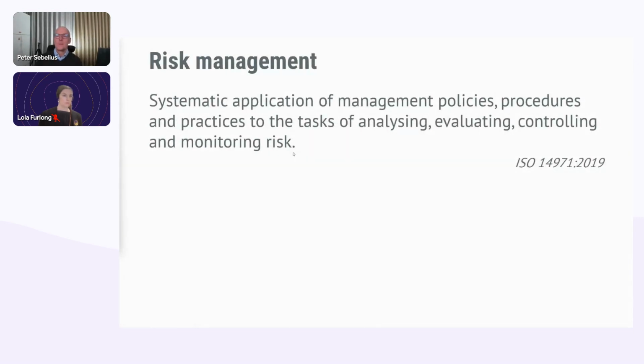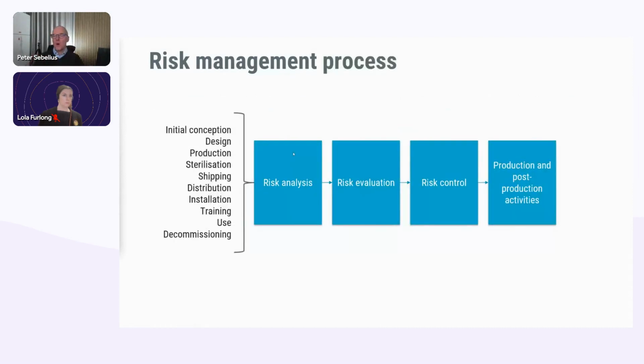That's the definition, though. If we take a look at it from a more visual point of view, what you are required to have is a process that includes risk analysis, risk evaluation, risk control, production and post-production activities that will address risks, all risks actually, from all the life cycle phases. And you see examples of the life cycle phases here. Yours might be different depending on the nature of the product, but these are quite typical, ranging from initial conception until final decommissioning. So this is what you need to do according to ISO 14971.